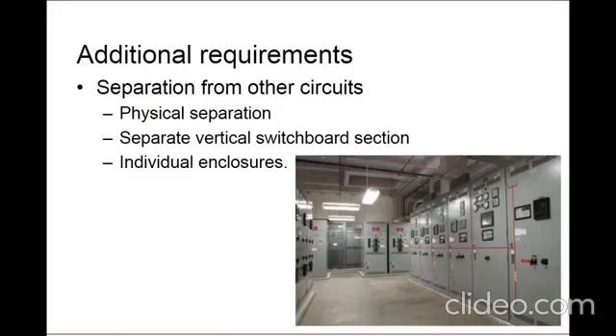As if all this wasn't enough, there are some additional requirements that you must be aware of in your system design. One is the requirement for the branches to be separated from other circuits. Now, Rob touched on this from a branch circuit level. The codes also talk about this all the way up at the distribution level. The requirement lists that branches must include physical separation from each other. This can be done two ways, either with vertical switchboard sections, which is the most common, or you can also do it via separate enclosures, such as a set of enclosed circuit breakers lined up near the generator.